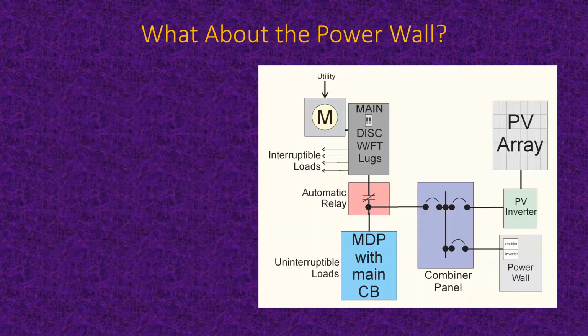All right, here's our Powerwall. Does it look familiar? Powerwall is an AC coupled system. You see the main meter. You've got a main disconnect with feed through lugs and interruptible loads up there, because that automatic relay is part of the Powerwall system. And that automatic relay shuts down the connection between the utility and the rest of the world here if the utility goes down, because you're not allowed to dump power onto the utility when its voltage goes to zero.